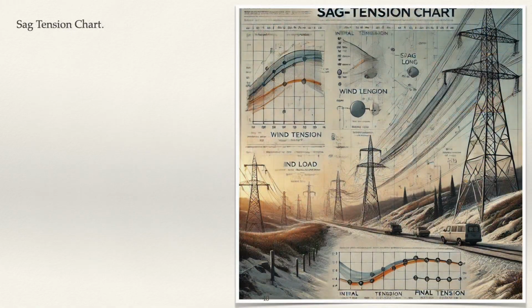Sag tension chart. To simplify field operations, sag tension charts are often created, showing the relationship between sag, tension, temperature, and span length for specific conductors. These charts allow field engineers to quickly determine the appropriate sag during installation.